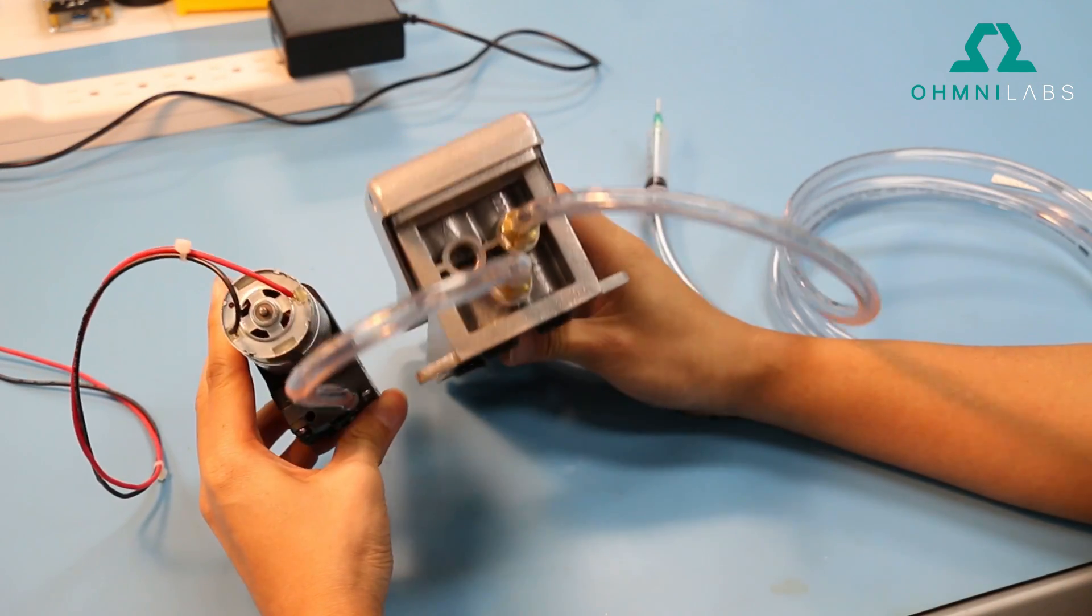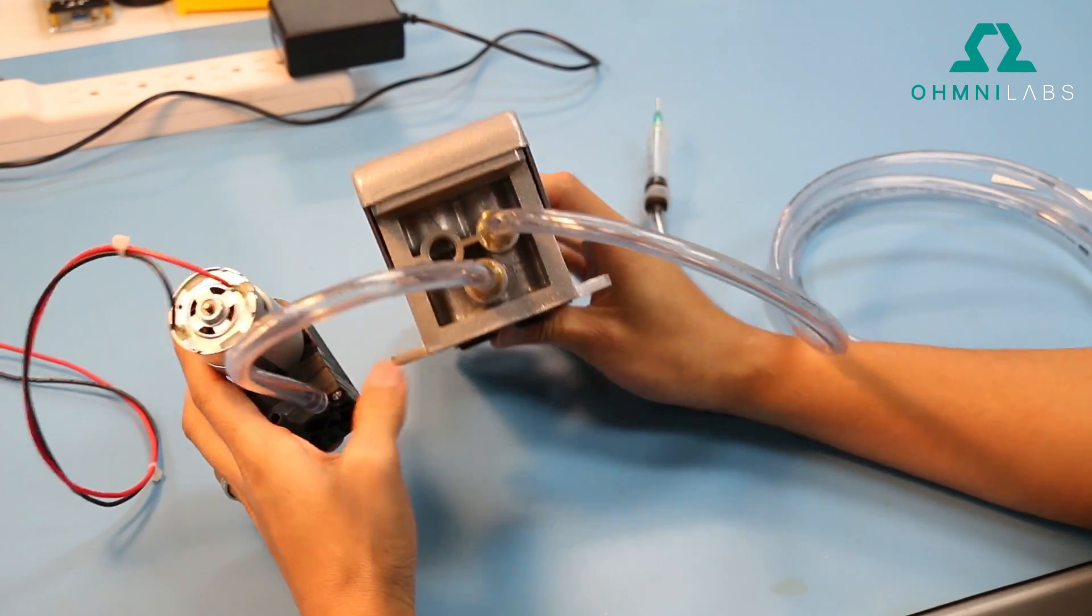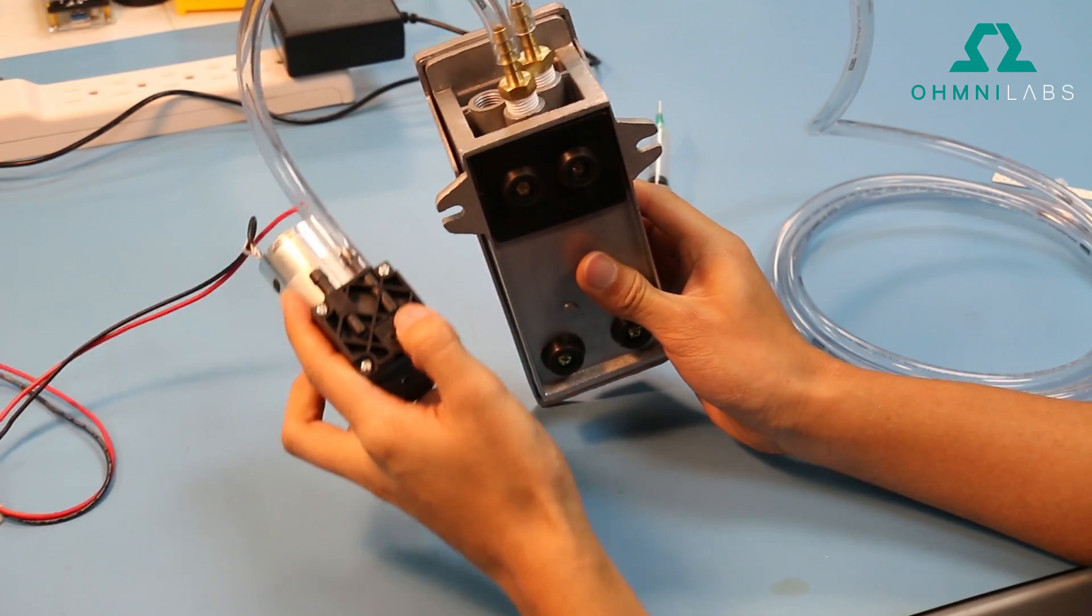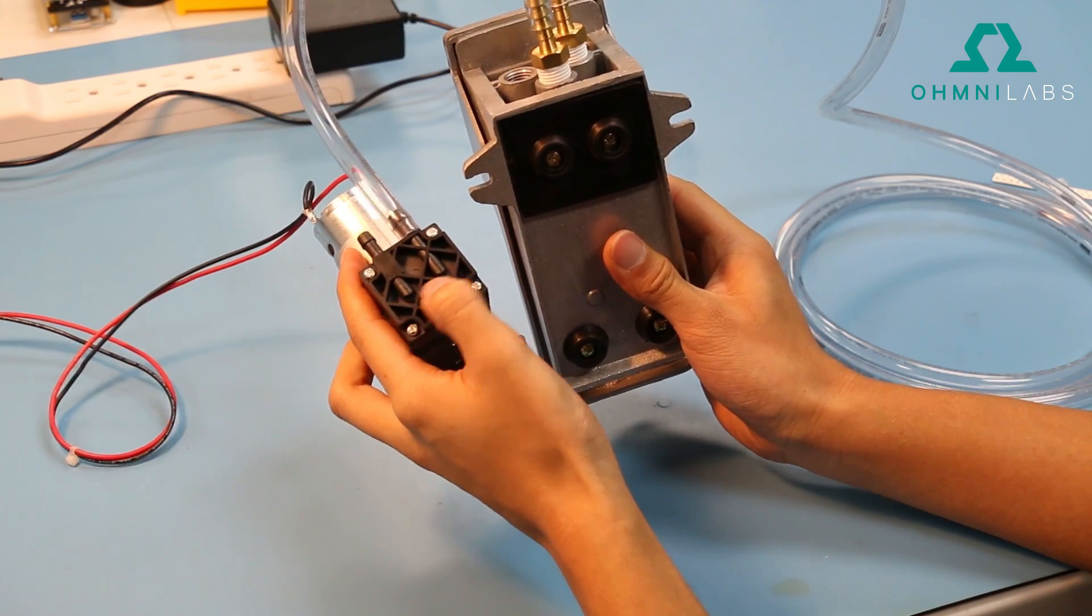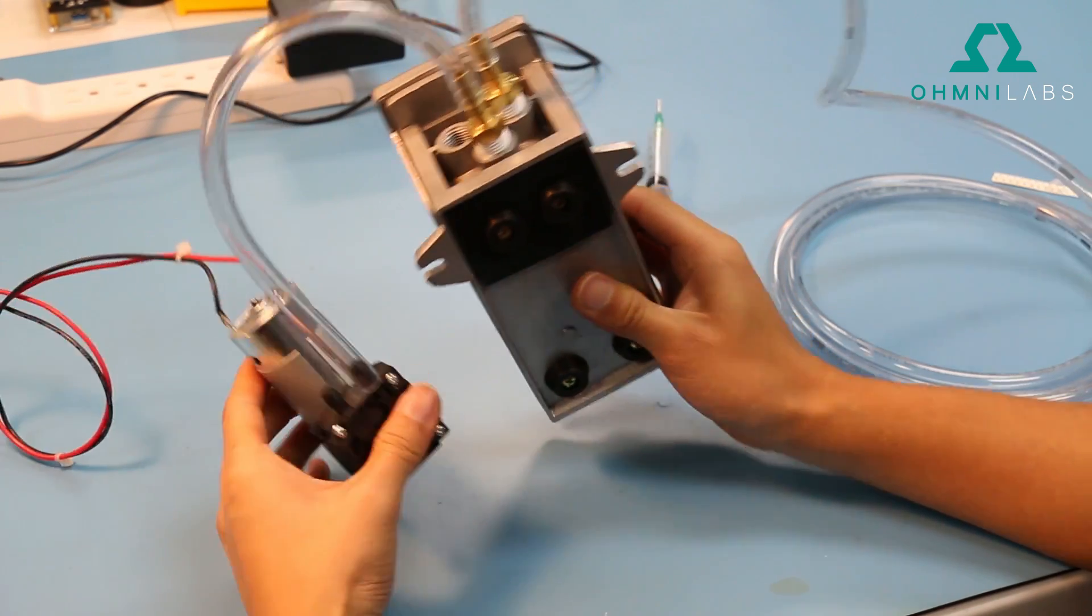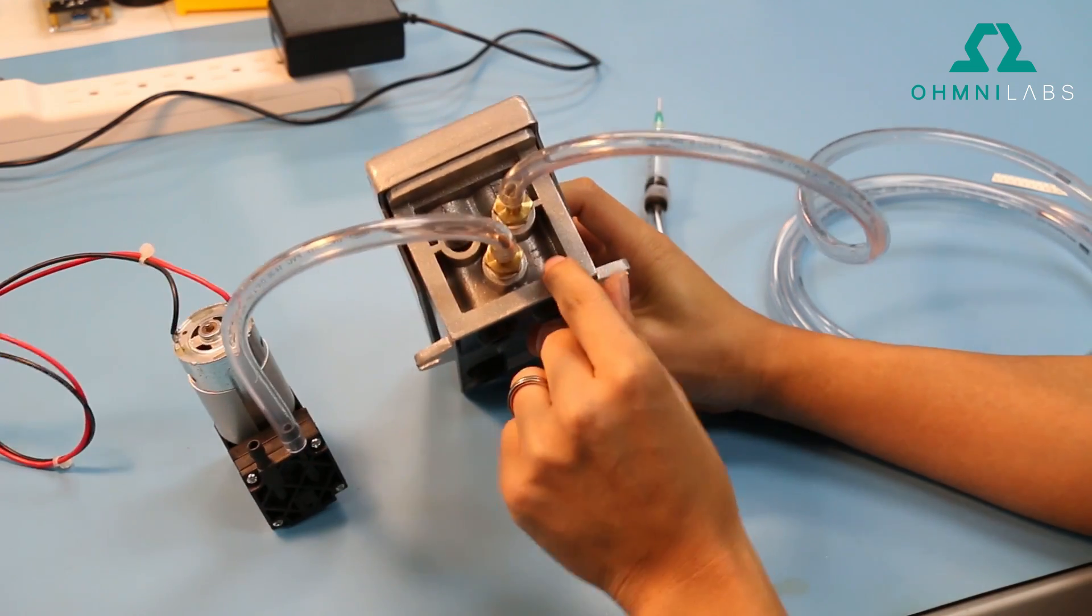Alright, so here's a bit more detail on the connectors for all the tubing. So this is the vacuum pump. You can see on the bottom they mark which way the airflow goes. So we connect the one that's pulling in on this side that goes to the bottom port P here.